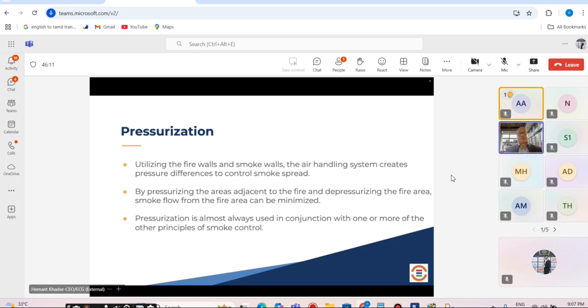So when you design a pressurizing system, it has to be seen how it is going to impact and intercommunicate with the other systems available. It could be the pressurizing systems from the other side. It could be the activation of the sprinkler system, which will again reduce the smoke propagation. It could be the door force, which is going to impact. It could be the number of openings for evacuation, ingress and egress both.